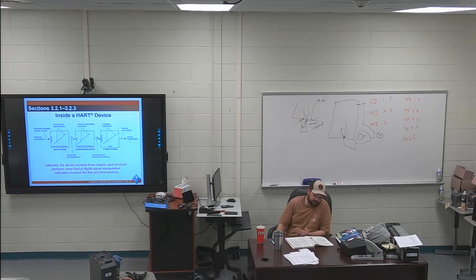So you read about the input stage, nothing highlighted in there. The middle stage, 323, I've got the first two sentences highlighted. When both the input and output stages of a HART device are calibrated, it should operate correctly. No calibration is required for the second stage because it only performs calculations.